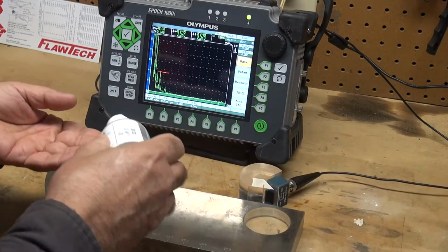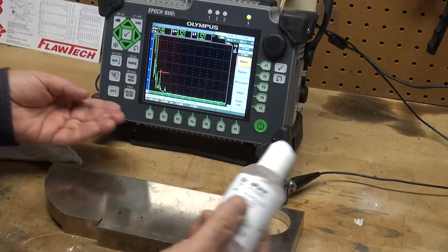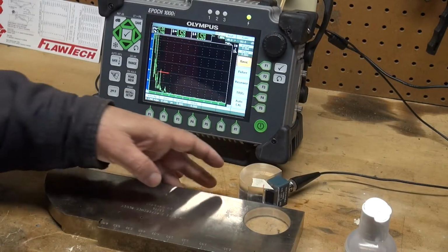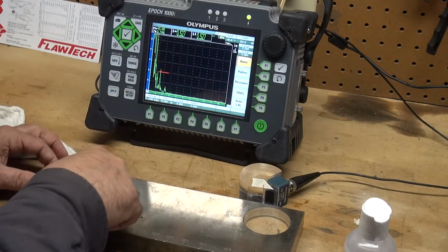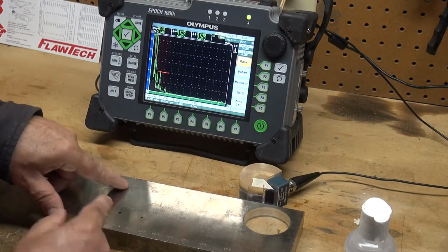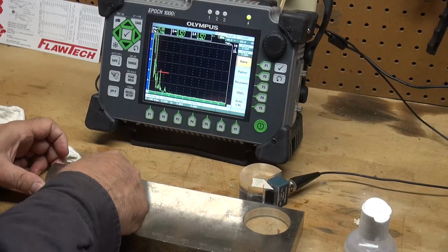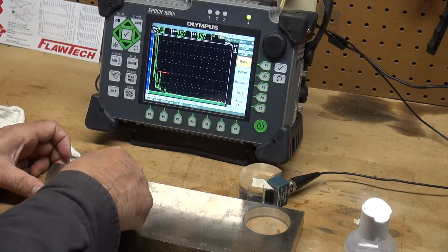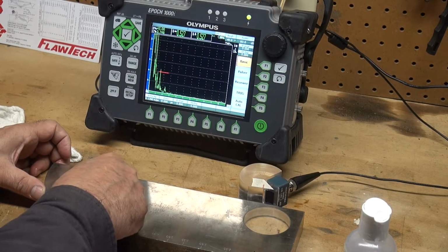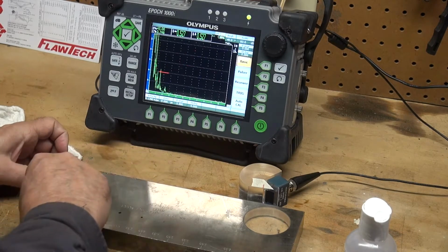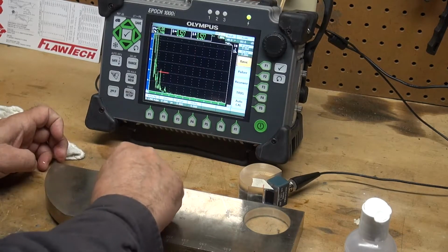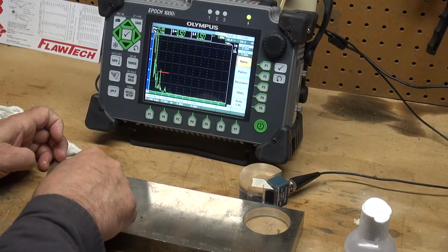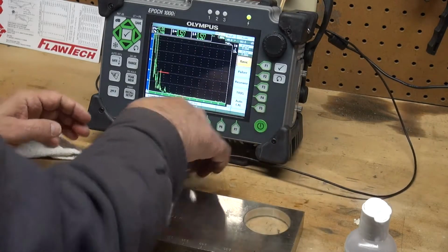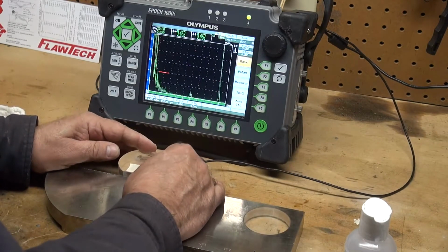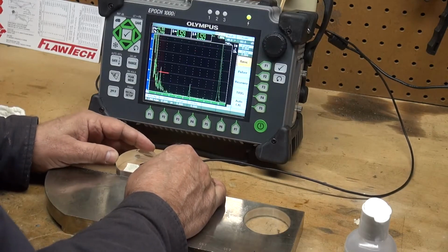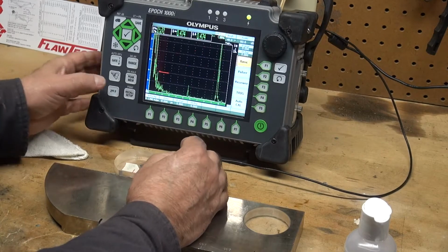So I'm going to put some coupling on my IIW block, and right here is a 0 marking. That is the machine mark on the IIW Type 2 block. From this point to this radius is 4 inches, and then on the other side is that 2 inch radius. So I'm going to couple my transducer to the block, and I see 2 reflectors.